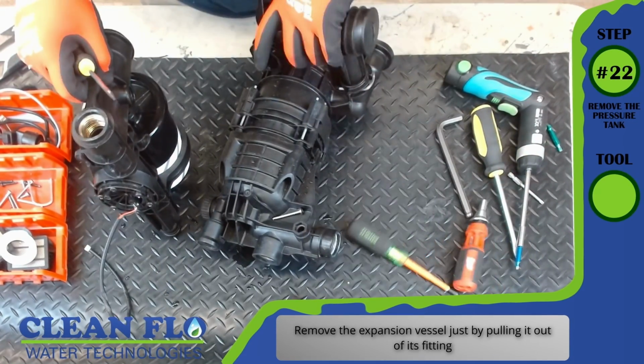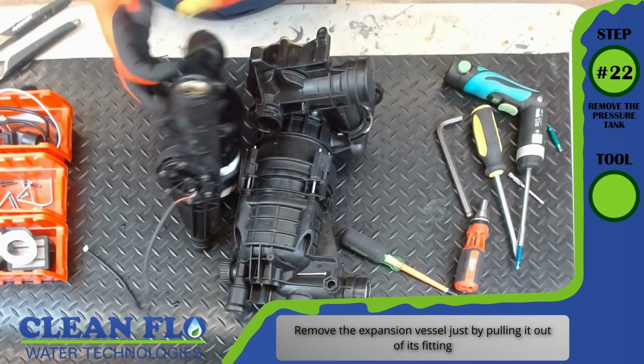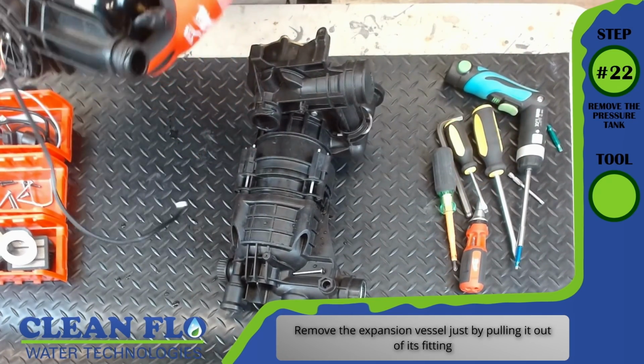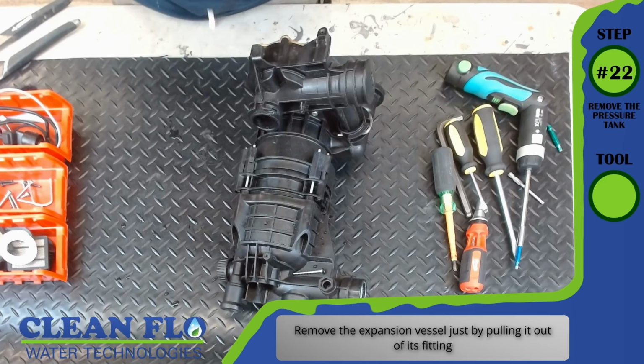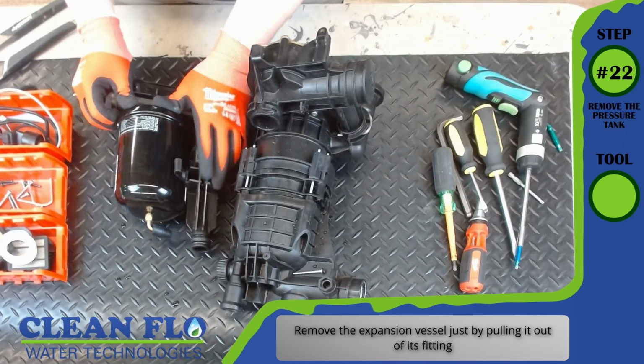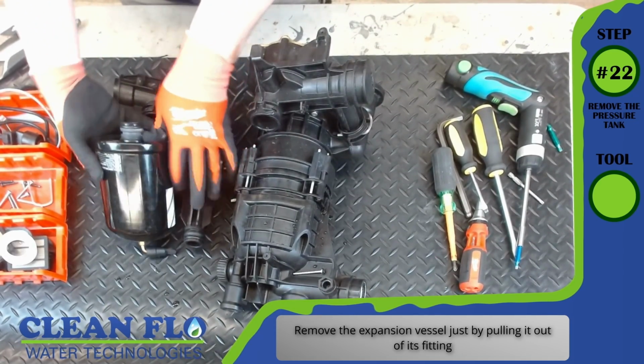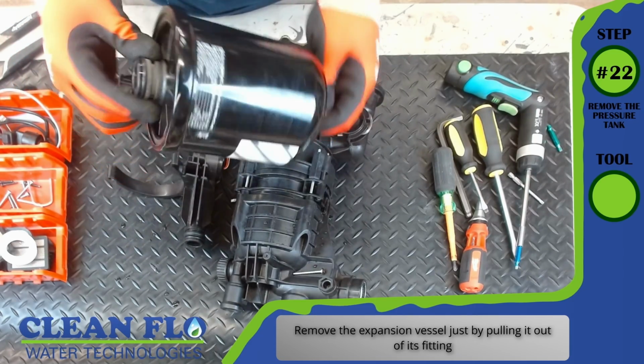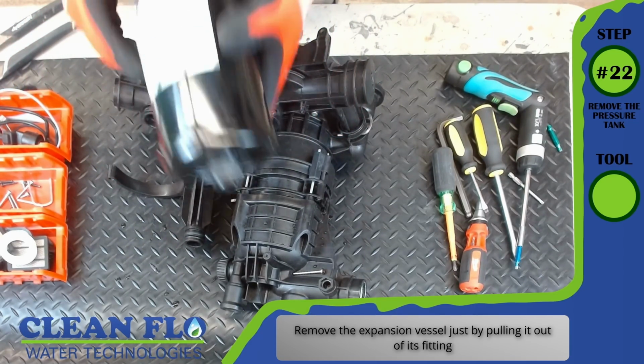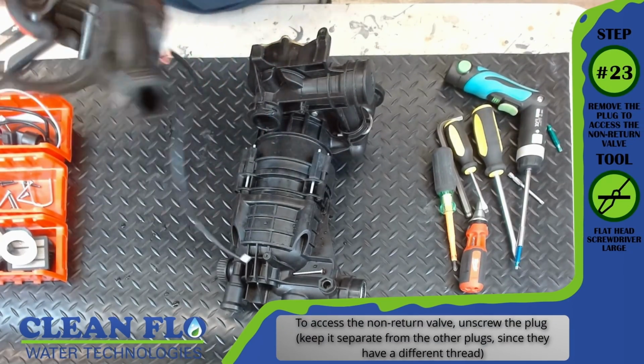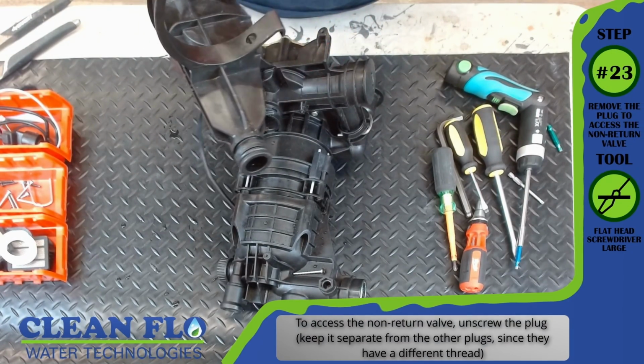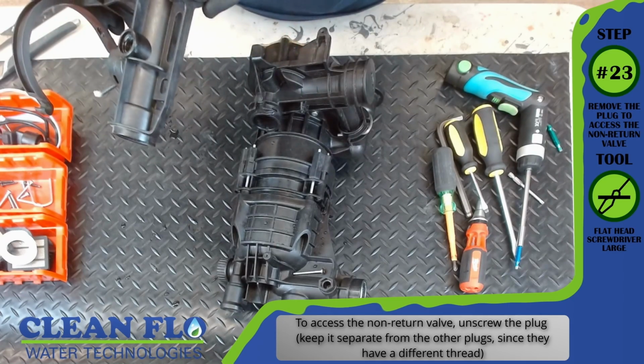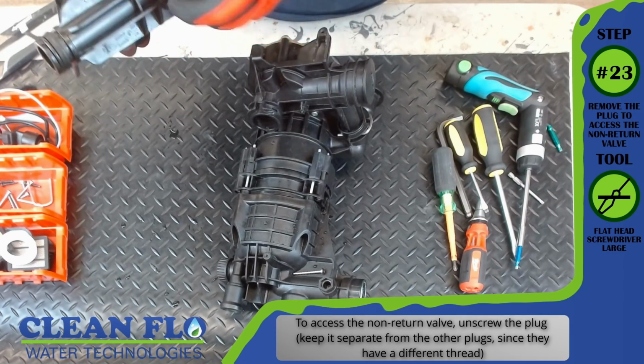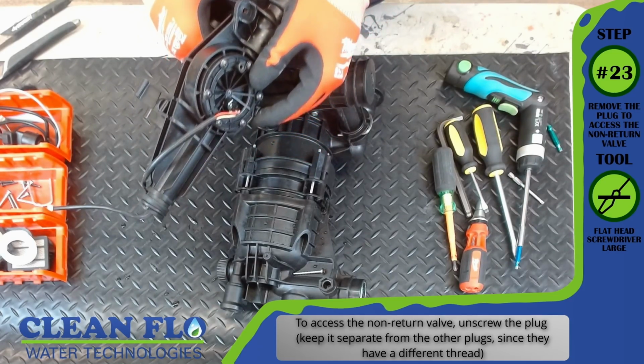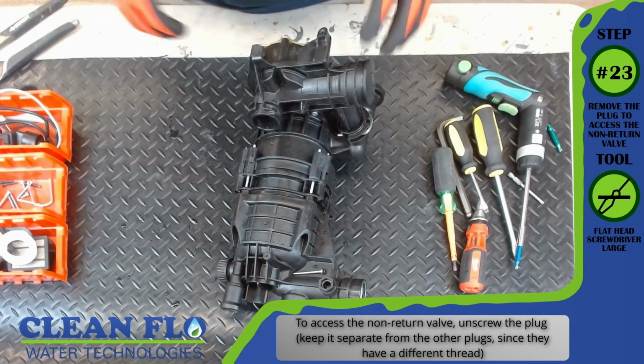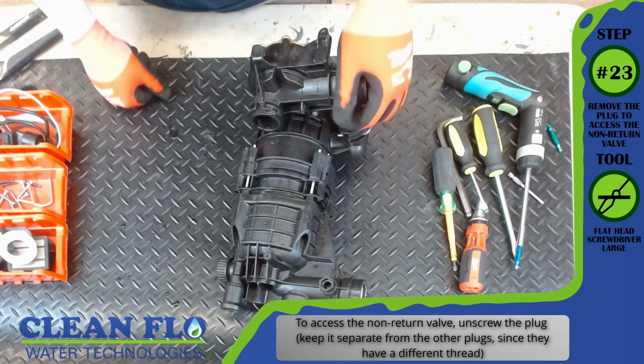Step 22, remove the pressure tank. No tool is required. Remove the expansion tank vessel by pulling it out of its fitting. This is the internal pressure tank inside the pump. Step number 23, remove the plug to access the non-return valve. Tool, flathead screwdriver, large. To access the non-return valve, unscrew the plug, keep it separate from the other plugs since they have a different thread.